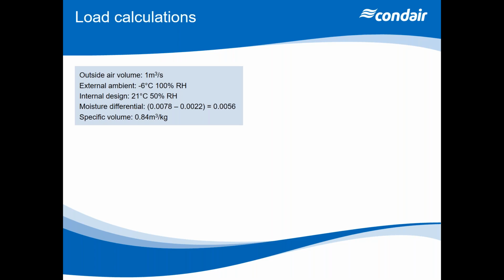Typically we use the units of meters cubed per second. So we want to know the outside air volume, not necessarily the total air volume, because we'd only humidify the fresh air makeup. So for instance, if you've got a 90% recirculation, we're only going to be humidifying 10% of that air, because all the rest of the moisture will be retained. We'll want to know the external ambient, and it's pretty common to be around -6 saturated at 100% RH. And we'll want to know the internal design condition, 21 at 50, let's say.